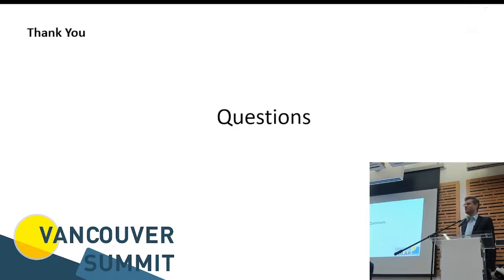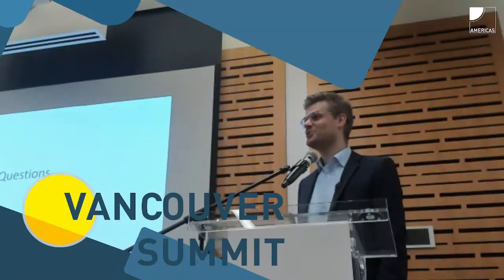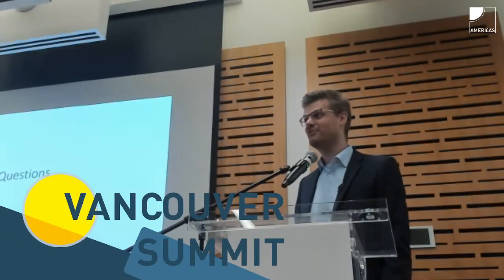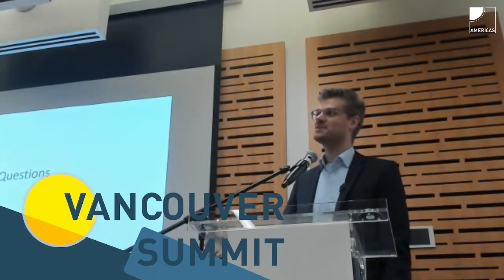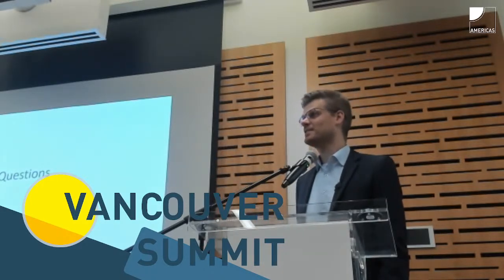So in the future, once the Fronius hybrid comes to market, and probably Harsha has more information than I do, it's probably going to be next summer. Exactly. That system will then also have a high voltage battery. There are some vendors that are already compatible with the European product from Fronius. We assume that is very similar to what the application will be in combination in North America. The good news is that the battery system already has UL 9540A. So the Fronius hybrid inverter plus that battery system will also have UL 9540 system certification.